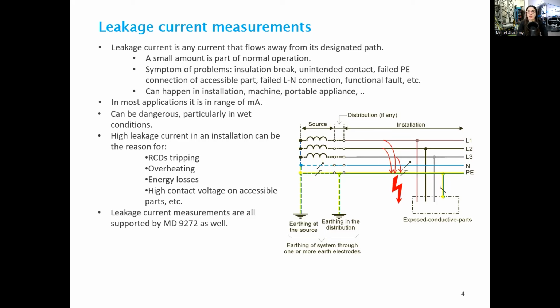Even during failure, usually the leakage current does not leave the range of milliamps, but it can still rise to dangerous values. Other problems that it can cause in installations, if it gets too high, are RCD tripping, overheating in parts of the installation, energy losses, high contact voltage on accessible parts, and other similar issues. Now, it has to be mentioned that all leakage current measurements are supported by the MD9272 as well, so with the old clamp. If we're talking about the locations and ways of measurements, we're talking about mainly looking at distribution boards, sockets, and device connections to the installation.